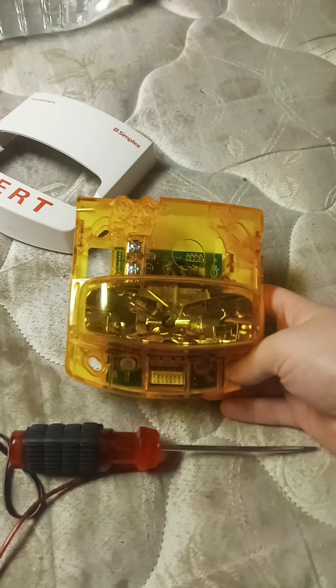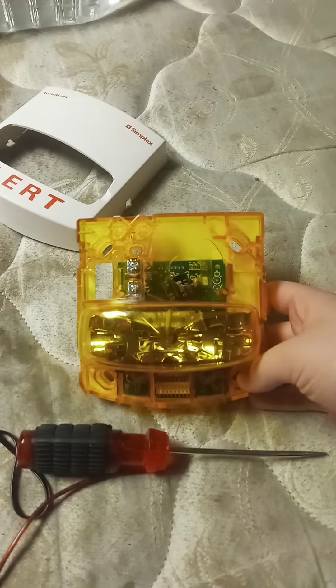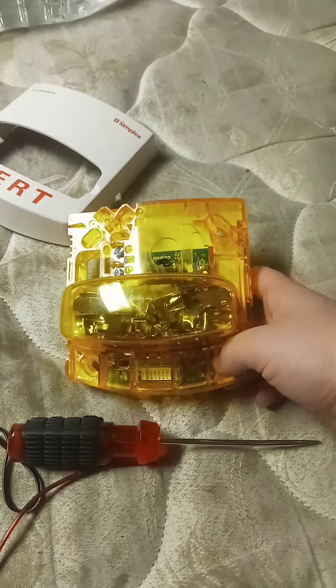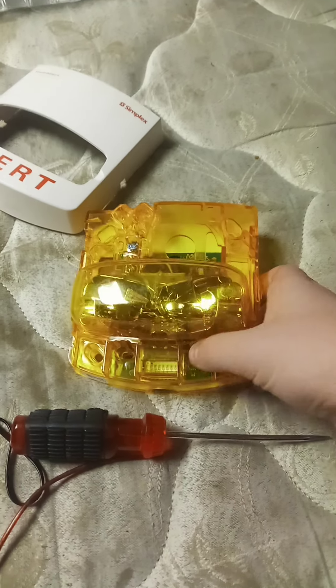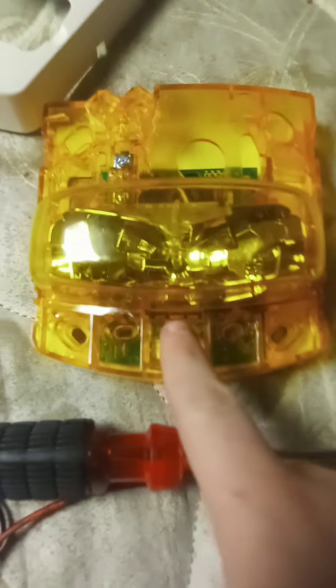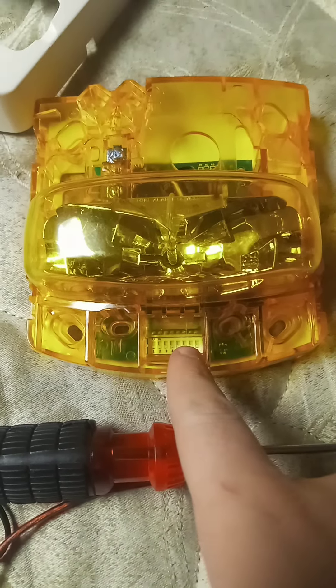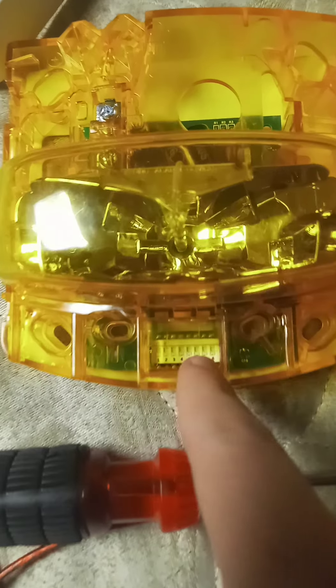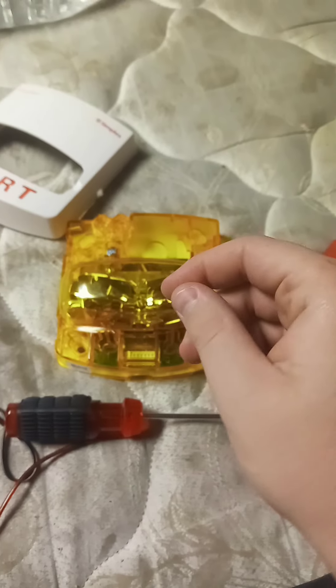This is an addressable device, so since it has the addressable line, it completely handicaps your ability to use it. The addressable line is the biggest handicap of all the TrueAlerts, including the TrueAlert ES. You can see this is what you use to set the address — it's 1 through 8, whatever's on and whatever's off confirms the address. There's an LED that blinks, and every time it polls, it's communicating with the panel.